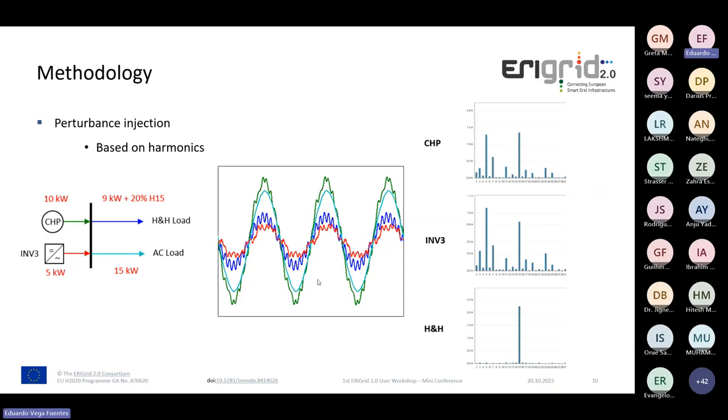And what we found was that on the generator side, the waveforms became highly distorted, and there were harmonics: the third, the fifth, 7th, 11th, 19th, 23rd. So we couldn't get any valid result regarding the share of the output from the generator.